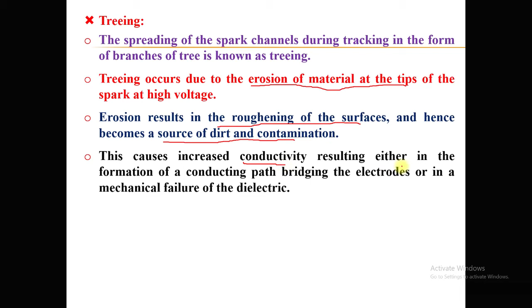So how can treeing be prevented? By cleaning the surface, by drying the surface, by repairing the damaged surfaces, or by having a clean environment. Materials chosen should be resistant to tracking. Sometimes moisture repellent greases are used to avoid not only the treeing phenomenon but the tracking phenomenon as well. Okay, but it needs frequent cleaning and re-greasing. Generally the treeing phenomenon is observed in capacitors and cables.